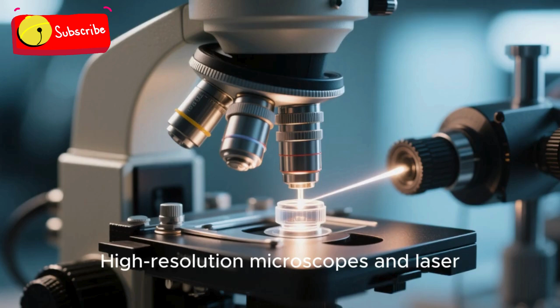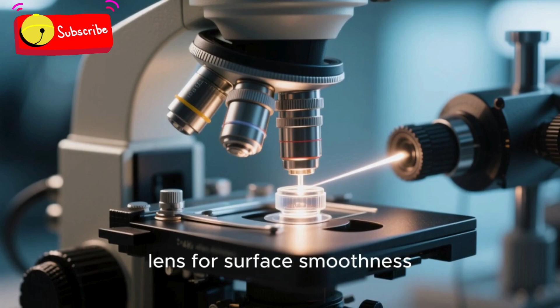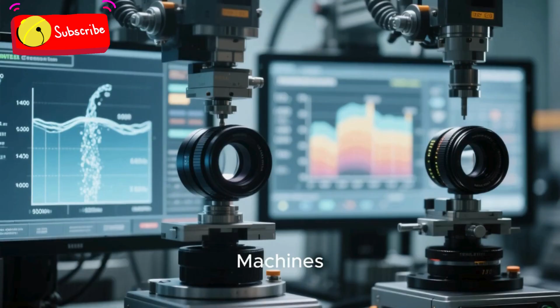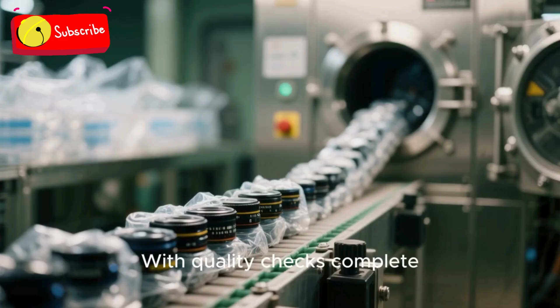Factories use a battery of high-tech inspection tools. High-resolution microscopes and laser scanners check each lens for surface smoothness, edge precision, and optical clarity. Automated cameras verify that the shape and curvature match the original design specifications down to the micron. Machines also test the lens's water content, its oxygen permeability, which is crucial for eye health, and its flexibility. Any lens that fails even one of these dozens of tests is immediately discarded. It's a ruthless process, but it's what guarantees your safety.